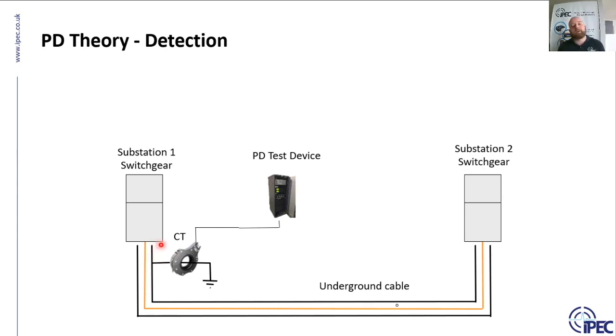Either an installation engineer has made a mistake, or it's not a standard policy to isolate the earth from the switchgear. When we get to the higher voltages, the HV level and the EHV level, when we're in the hundreds of kVs, obviously the earth is definitely isolated from the switchgear. But in the lower voltage levels, this may not always be the case, and it's always worth checking that situation out before looking to apply this type of technology.